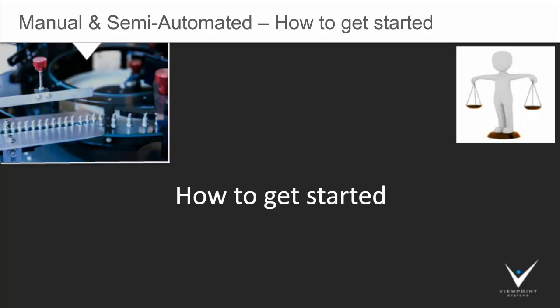To start with, some of the recommendations we made in the earlier slide on how to get a handle on automation. Some of the big hitters that we've found are reducing handwritten transcription errors to minimize passing of bad parts, a foot switch to trigger measurements automatically when you need to have your hands involved in connecting the probes for making the measurements, retrieving assembly instructions electronically rather than flipping paper pages, and finally creating reports automatically rather than by hand. These and other steps can generate cost savings by speeding up the testing time and by reducing the cost of manual labor associated with report generation and handling bad parts.